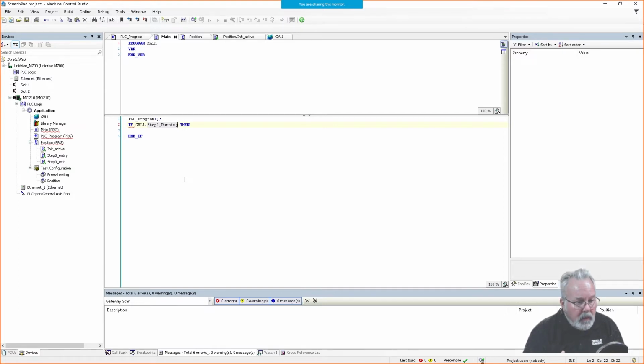So again, you can have multiple global variable lists, but they must be given a unique name. And when you want to utilize any of the variables found in that list, you must preface your statement using the name of the list that the variable was declared in. So you're going to find yourself using these pretty frequently.